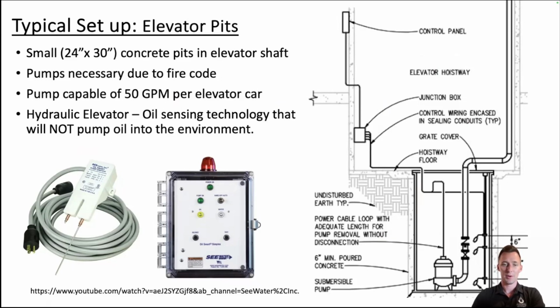The one wrinkle is how to design for a traction elevator versus a hydraulic elevator. Traction elevator is more common nowadays, becoming kind of the go-to. I would say with a standard sump pump and panel, you have no worries there. A hydraulic elevator has hydraulic fluid present, and the plumbing code says that we cannot pump that hydraulic fluid or oil, hydrocarbon, out into the environment. So you need a way to leave that in the pit and still continue to pump, or never shut down this pump in case fluid or water is coming in to fight fires. It's a fire code issue.